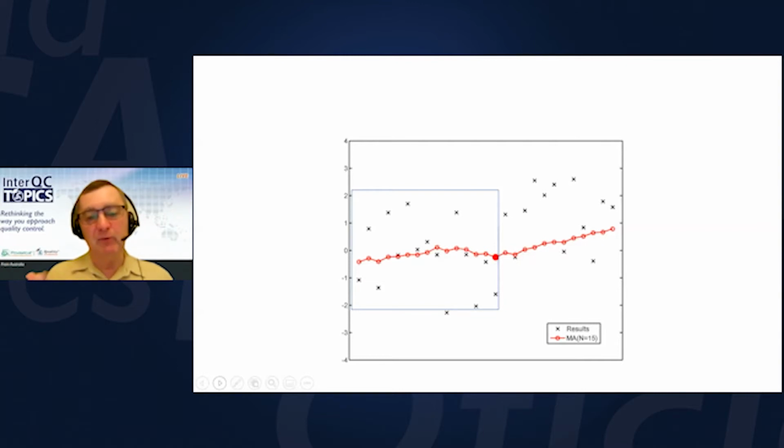I'm sure everybody who's run an analyzer at some stage, perhaps running sodiums or glucoses or hemoglobins, often has a gut feeling that there's something wrong with the assay. For instance, with sodium, for normal patients, or even for most patients in a hospital situation, you expect sodiums to be around 139 to 142 millimoles per litre. If you start to see a whole lot of patients with results around 144 or 145, you think something has gone wrong because you just don't normally see that. So that's what patient-based real-time QC is.